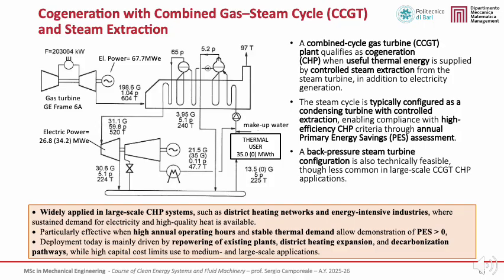A combined cycle gas turbine plant qualifies as cogeneration or CHP when useful thermal energy is supplied to an external user by controlled steam extraction from the steam turbine, in addition to electricity generation from both the gas and steam turbines. In this configuration, the steam cycle is typically arranged as a condensing turbine with controlled extraction. This layout provides operational flexibility and allows the plant to comply with high-efficiency CHP criteria, which are assessed on an annual basis through the Primary Energy Savings, or PES, indicator.